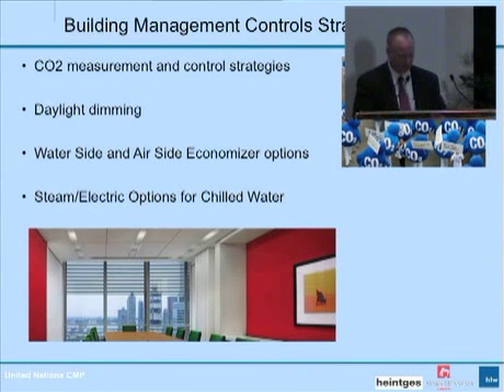As I mentioned before, our steam electric hybrid chiller plant: we have 3 electric chillers at 1,800 tons, and 2 steam chillers at 2,500 tons. Conduits are bringing in steam at 150 pounds, and we're using that steam not only for cooling for peak, we're also using it for heating and domestic water.